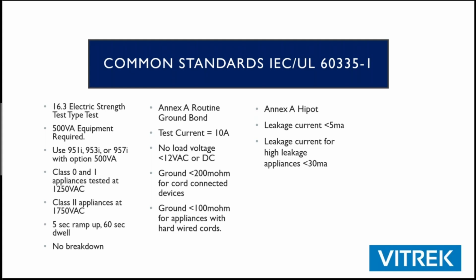So the concern is that early HIPOT testers only measured the output on the primary side of the transformer. So if you didn't have a large enough power output, you could collapse that output and there would be no way to verify that you were getting the proper test voltage at the DUT. So that's kind of a holdover portion of the standard there. And oftentimes there's workarounds for that if you don't want to use a 500 VA rated piece of equipment. But we do offer those.